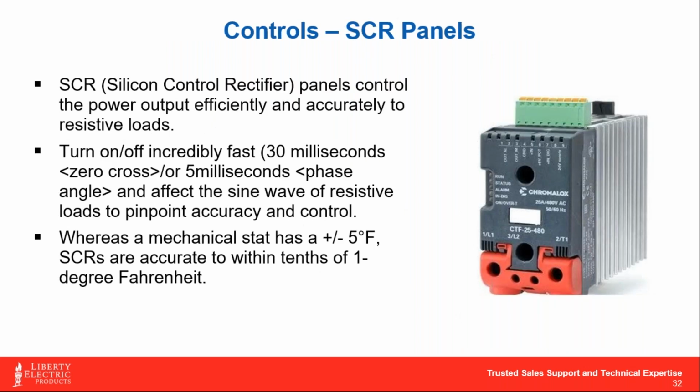This is my favorite one, the SCR panel. I really like solid state relay based controls. The easiest way to describe these is that they turn the heater on and off so quickly. You're basically playing with the sine wave, the energy wave of the electricity, to affect the current going to the heater itself.